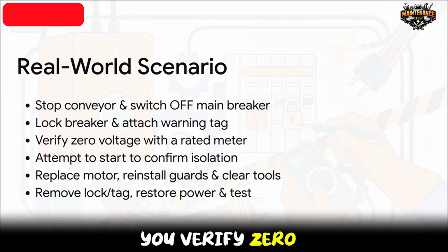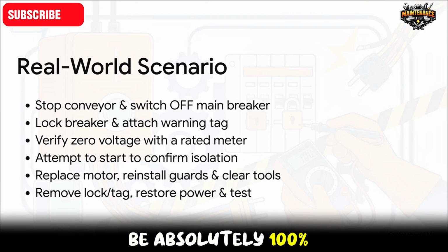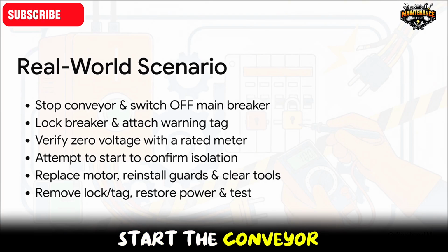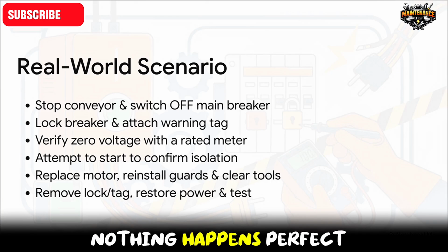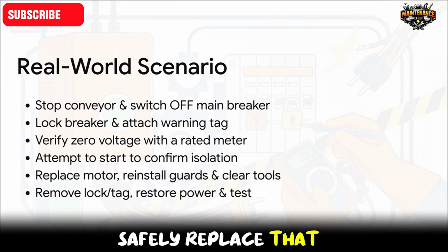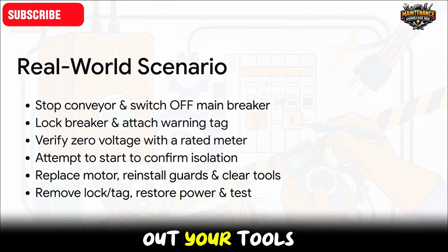Next, you verify zero voltage using a properly rated meter, and just to be absolutely 100% sure it's dead, you attempt to start the conveyor from the operator controls. Nothing happens? Perfect. Now you can safely replace that motor, reinstall all the guards, and clear out your tools.